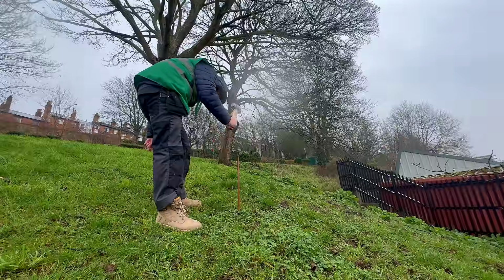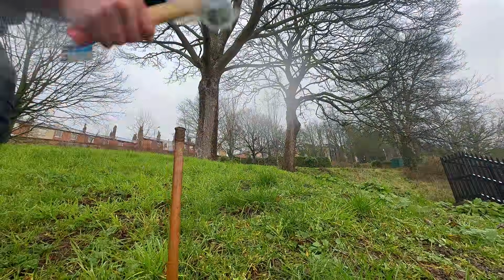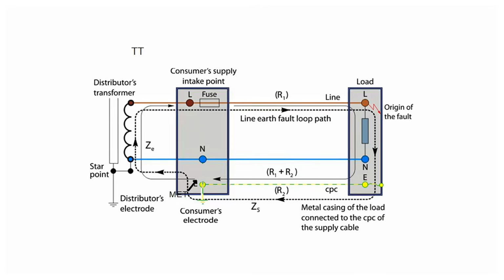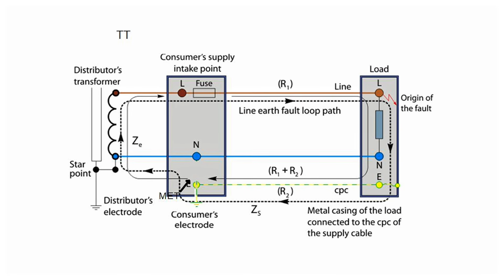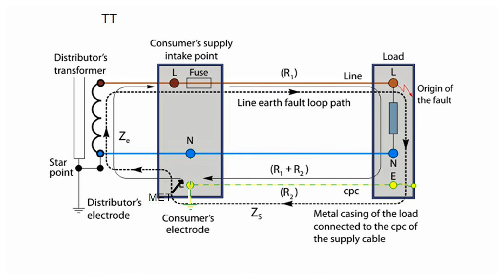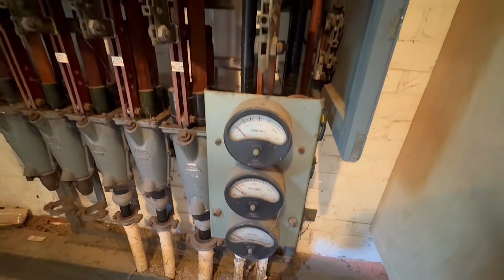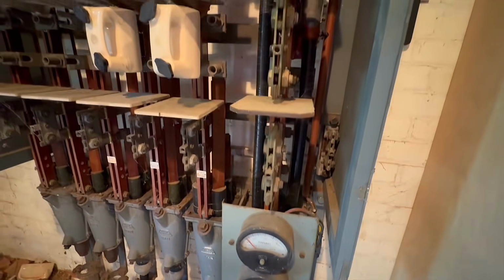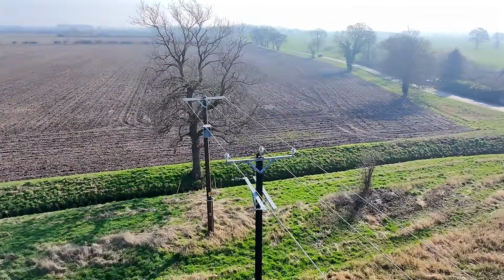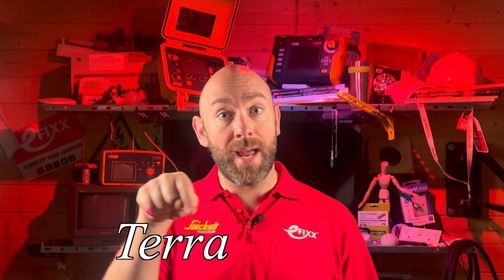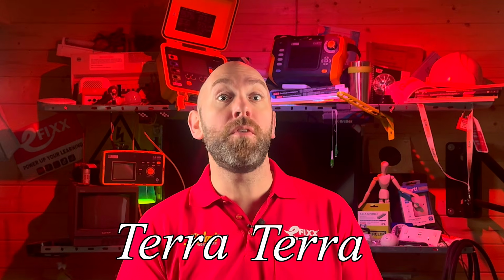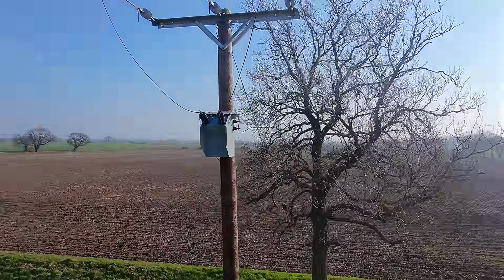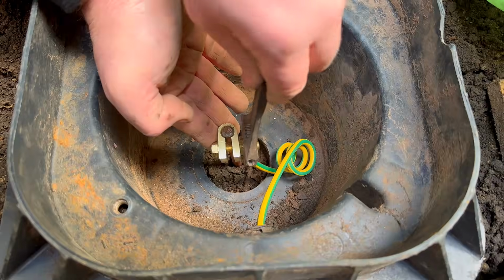An earth electrode is simply a conductive part that is intentionally connected to the general mass of Earth. Its job is to provide a path for fault current to leave the installation and return to the source. In many installations, the electrical distributor or DNO supplies that earth for us, but in a TT, they do not. TT? TT stands for terra terra, and terra is Latin for earth. So a TT is basically one terra at the source and another terra at the supply.